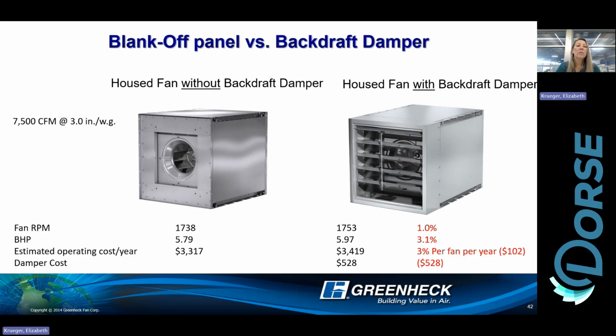That means we're going to be using 3.1% more power just by adding a damper in front of a fan. If you think about that over the longevity of a fan array, going in at 6 years per motor minimum, and you can still upgrade the motors and change out wheels if you ever need to, though I haven't come across that being an issue. These arrays are meant to be in there for quite some time.